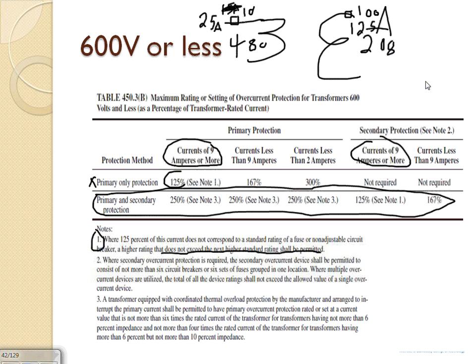I call it the receptacle transformer because you need this one only if you're feeding receptacles. A building like this, why do you need a 208/120? You can run the air handling unit at 480. You can burn these lights at 277, right? So why do I need it? The only time I need a 208/120, or especially 120, is for the receptacles. Almost all equipment can run at 277 or 480.